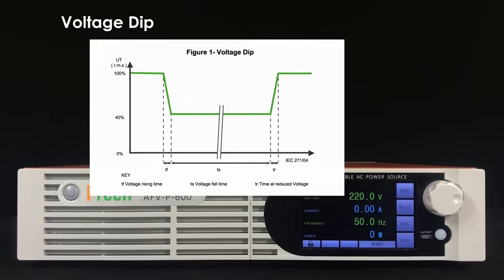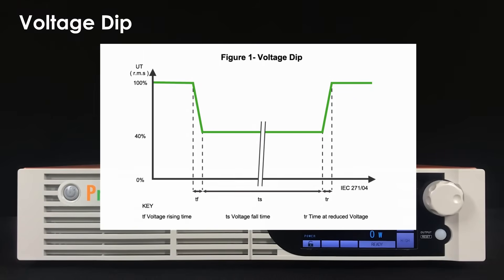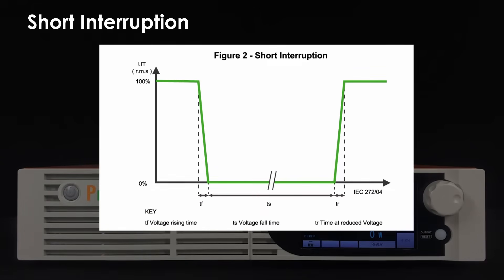A voltage dip indicates a sudden reduction of the voltage at a particular point of an electricity supply system below a specified dip threshold, followed by its restoration after a brief interval. A short interruption indicates a sudden reduction of the voltage on all phases at a particular point of an electrical supply system below a specified interruption threshold, followed by its restoration after a brief interval.